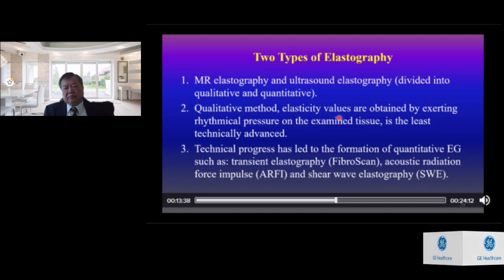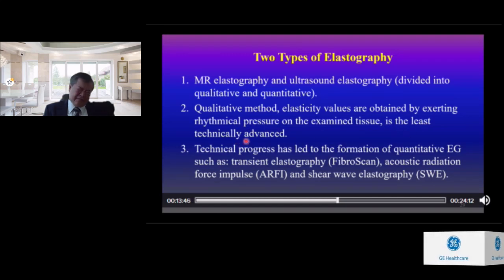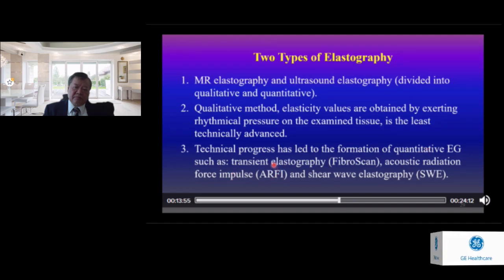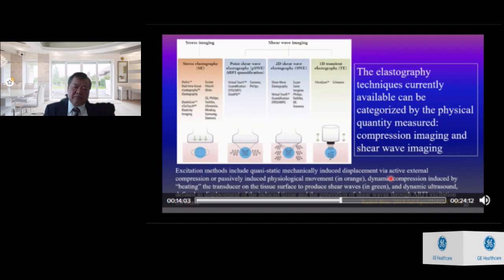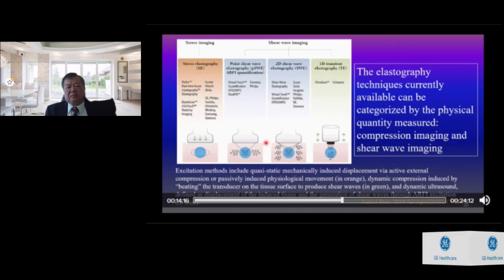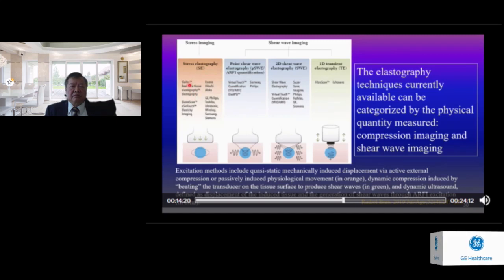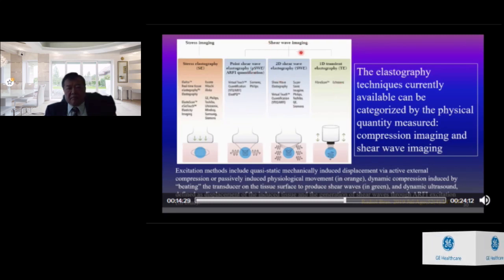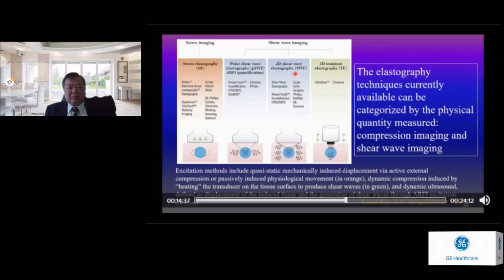Qualitative methods obtain elasticity values by exerting rhythmical pressure on the examined tissue. Technical progress has led to quantitative methods such as transient elastography (FibroScan), ARFI, and shear wave elastography (SWE). Elastography techniques can be categorized by physical quantity measures: compression/stress imaging, and shear wave imaging. The point shear wave is used in ARFI, and 2D shear wave elastography is also available, as is transient elastography in FibroScan.